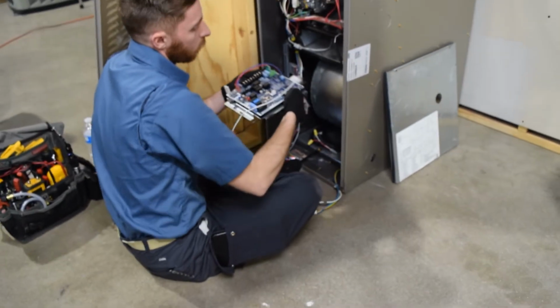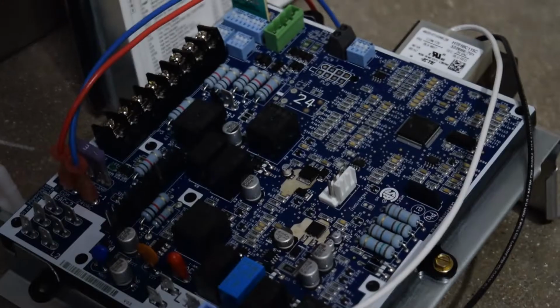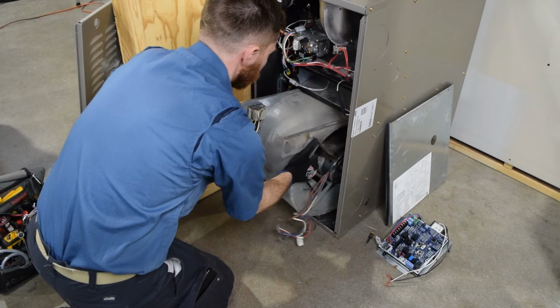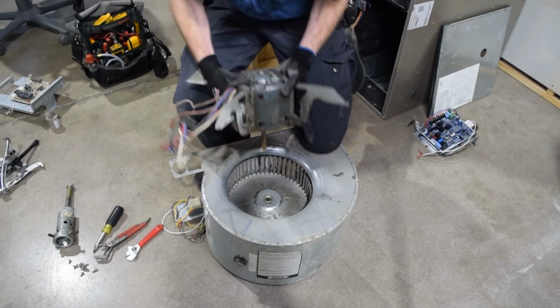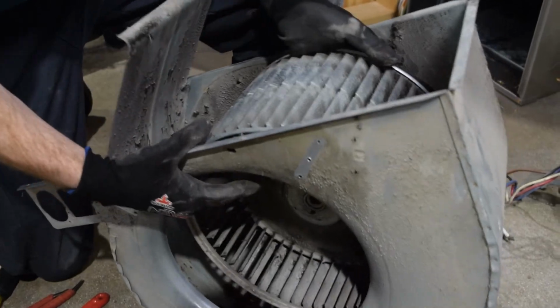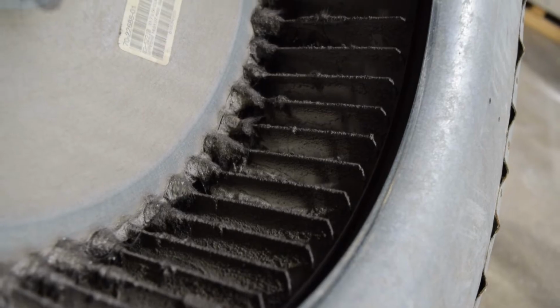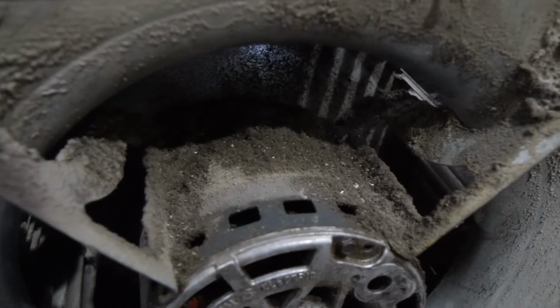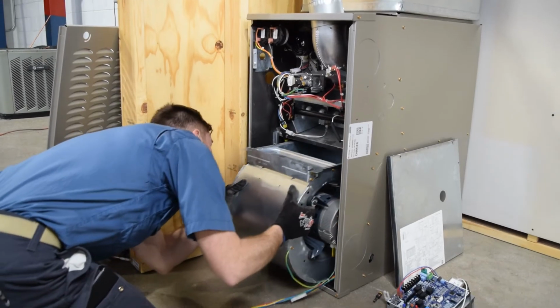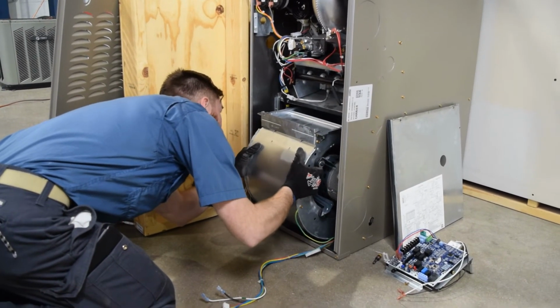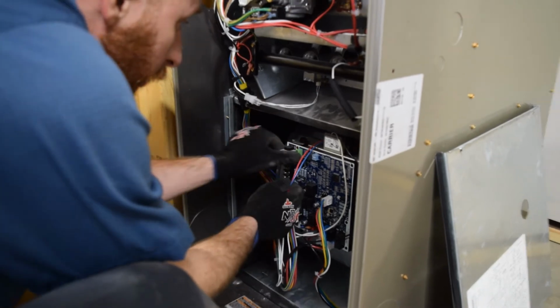First, I'm going to turn the system off and remove the doors. I'm going to remove the entire wiring and circuitry of this system, and then take the entire assembly that holds the motor and remove it from the furnace. After that's done, I'm going to totally disassemble and remove the motor from the housing and wheel, then use chemicals, cleaning, water, soap, and bubbles, everything needed to wash and clean this as thoroughly as possible. After that, I reassemble everything, install it back into the furnace, put the circuitry and circuit board back on, and then test run the system.